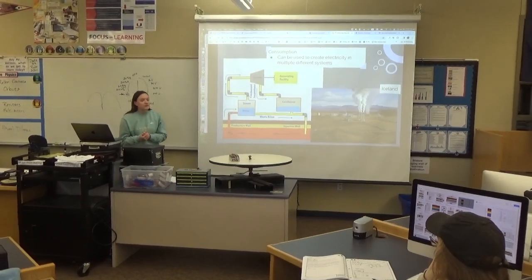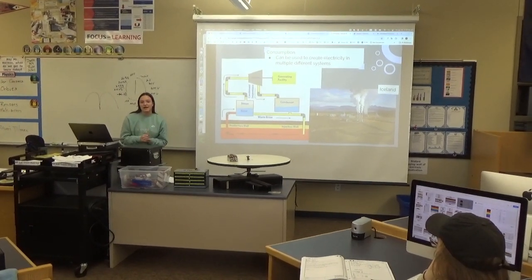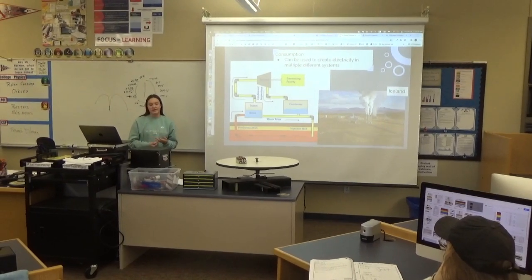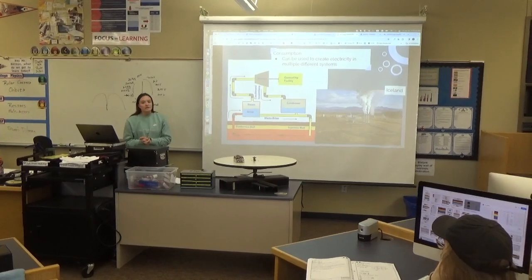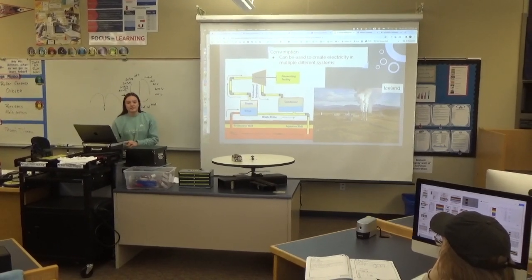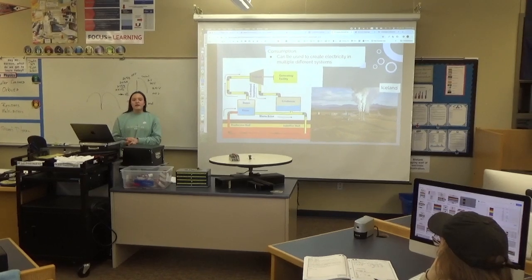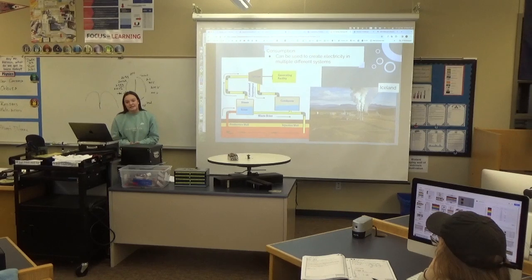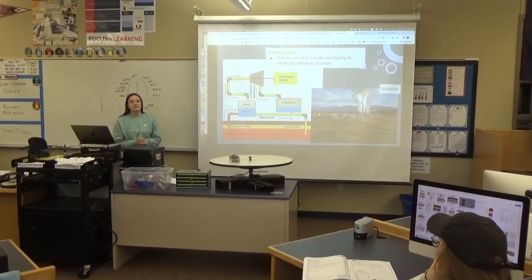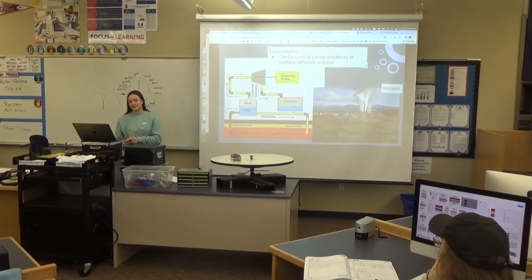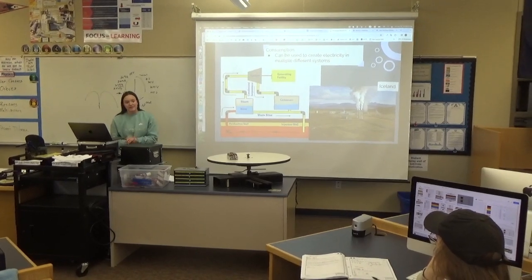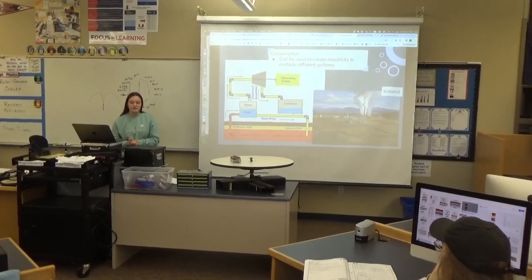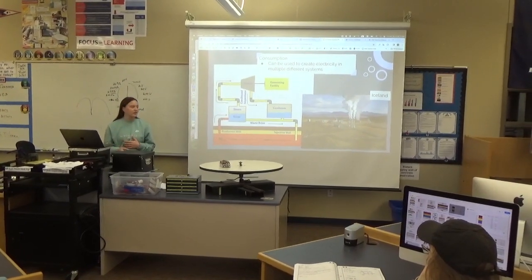When you're talking about geothermal power plants, there are three different kinds. You have dry steam plants, flash steam plants, which are the most common, and then binary steam plants. In a flash steam plant, you're tapping into a reservoir of water that's around 360 degrees Fahrenheit. So the water will flow up through a well due to its own pressure, and then as the pressure decreases, it's able to evaporate, and that steam is guided through a turbine, which is attached to a generator. After it moves through the turbine, it goes to a condenser, where it can be turned back into water and then returned to the reservoir so that the system can repeat indefinitely.